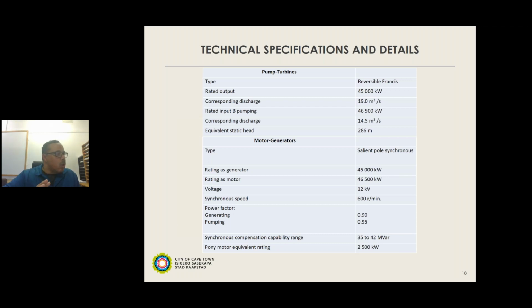Okay, and then last line, maybe of importance, or just for interest, the pony motor that we were referring to a bit earlier, the one that sits right on top, operates at 2,500 kilowatts. When we run in pump mode, I know it says 46,500 here, but it is a little bit more. When we have to pump at night, obviously it's going to require more power than what we can generate. So we always run at a net loss in terms of kilowatt and megawatt hours produced at any stage. We usually take about 52 megawatt per unit to get the water pumped back to the upper reservoir again.